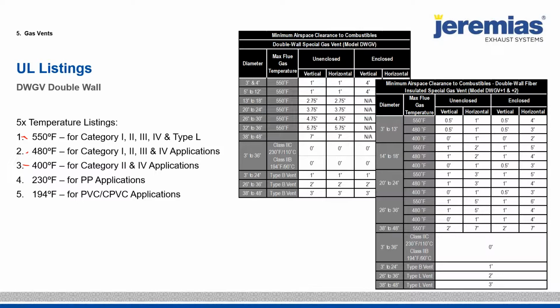So we did a 400 degree temperature listing so we could have 0 clearance to combustibles, taking advantage of that insulation, that fiber insulation that's automatically added on the Conical system as well. So we can actually get 0 clearance to combustibles on any condensing appliance, and then we actually got the product listed and approved for plastic applications as well. So you have 0 clearance to combustibles for all the plastic applications, both the single and double wall.